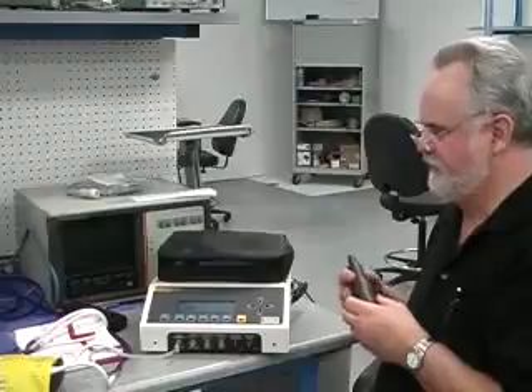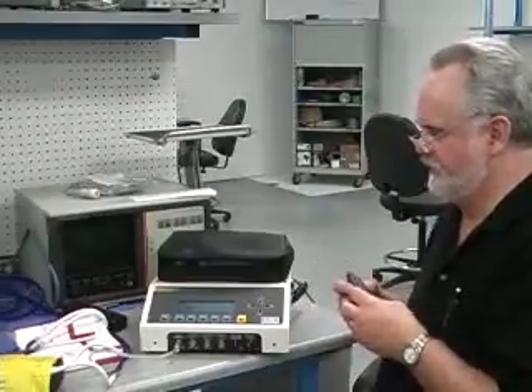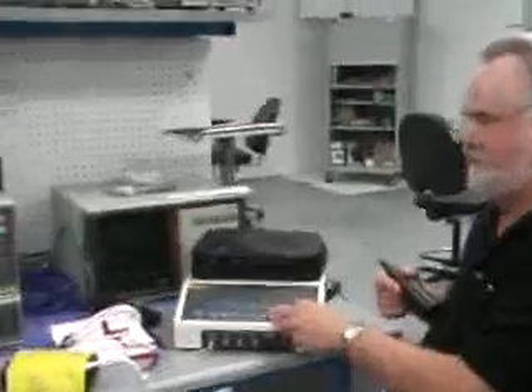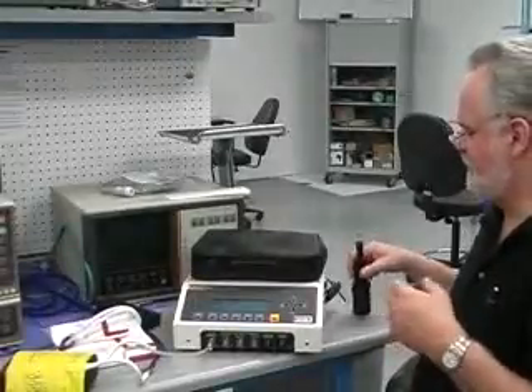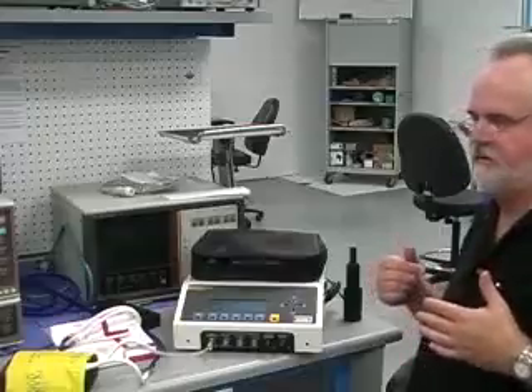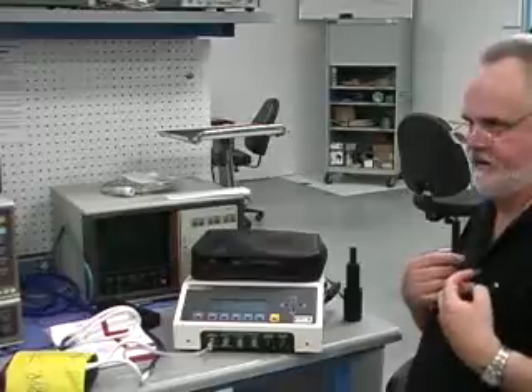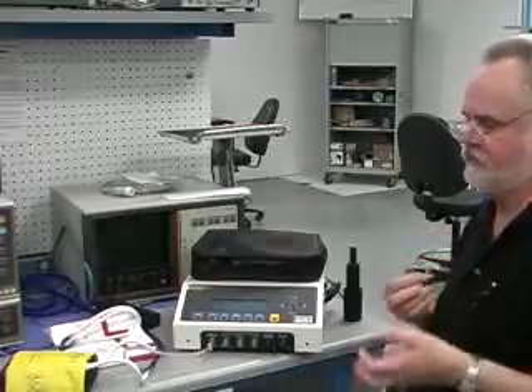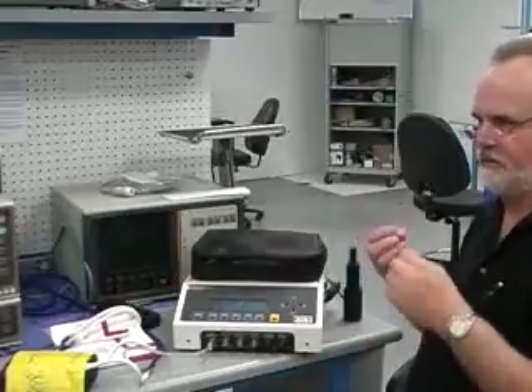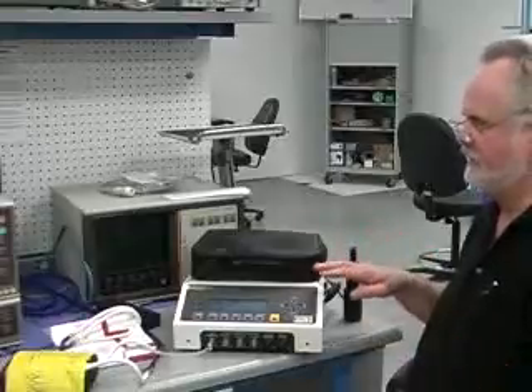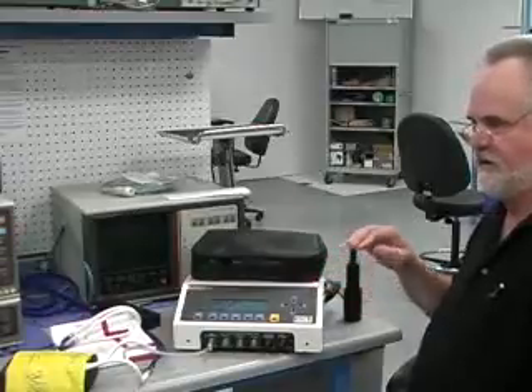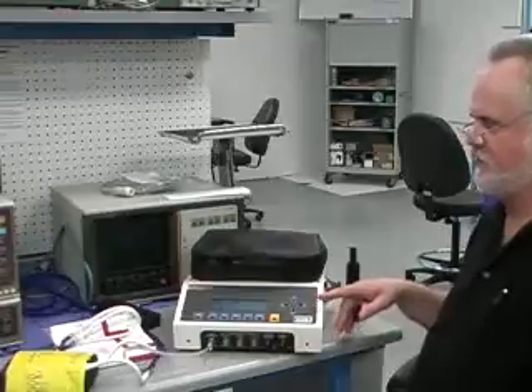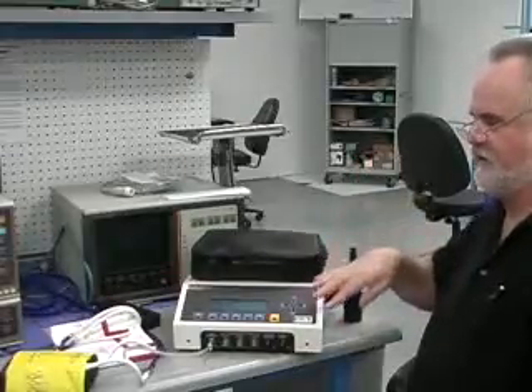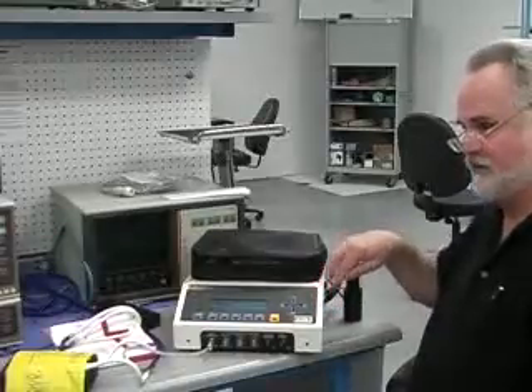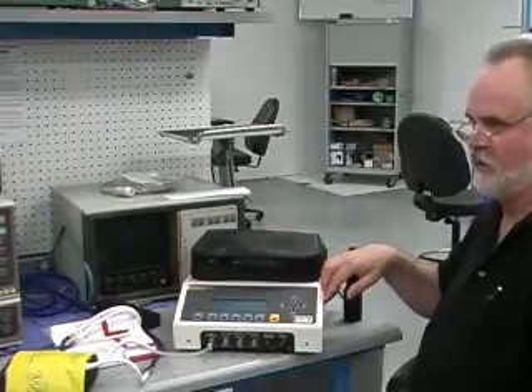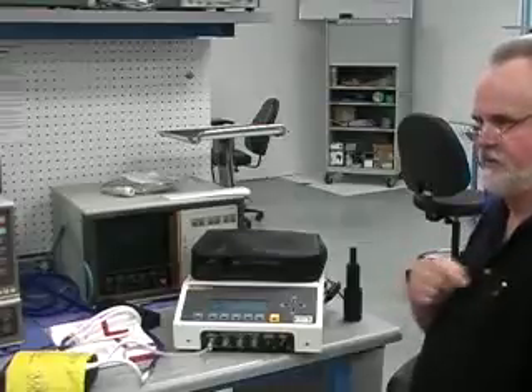There's just a series of a few, I won't say life-threatening arrhythmias, but there are just basically. What's different here is that if you're in a condition where your heart isn't beating normally, maybe you've got a premature beat, it could be a premature normal beat, or a premature ventricular beat, or an atrial fibrillation beat, where the interval between the R waves is different. We can simulate that too. Most NIBP devices should have the ability to work with basic arrhythmias. If the patient has ECG problems beyond what's in here, typically they would have an indwelling cardiac pressure line put in, and they'd be measuring the blood pressure directly.